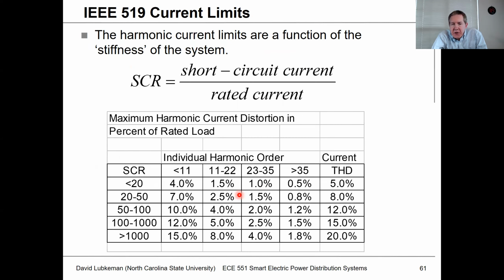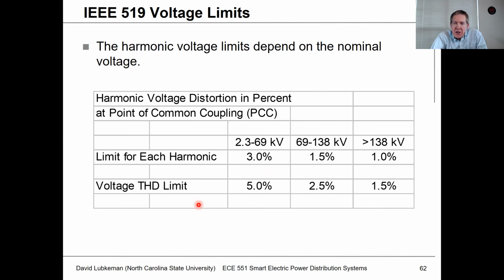So anyway, these numbers are designed in such a way that as long as these industrial customers stay below this point, then you're going to be okay. However, what happens if you have multiple industrial customers that are injecting? Well, then that effect's going to be additive. And then if you get the harmonic voltage up above a certain level, then motors are going to start overheating and transformers are going to start overheating and other things are going to start to happen, right?